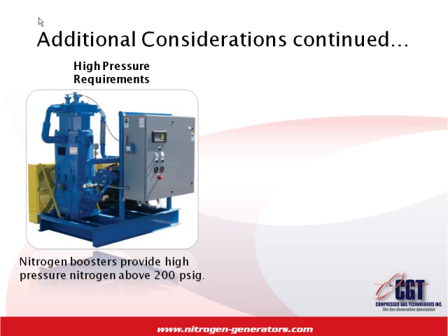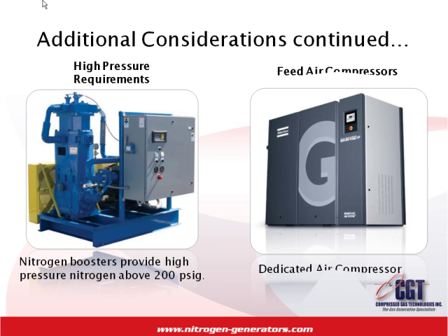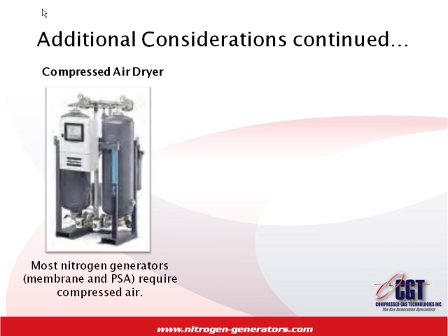In some cases, customers do not have enough compressed air or high enough pressure, and in these cases a dedicated air compressor will be required. Almost all nitrogen generators, both membrane and PSA, require dry compressed air. If the air quality feeding the nitrogen generator is not adequate, a dedicated air dryer may need to be installed ahead of the nitrogen generator.